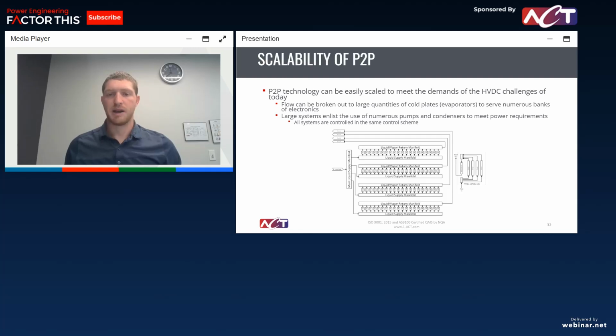So you can see on the bottom there just a picture of how we've done it before. Each of those little boxes that you can barely see there has 5 cold plates in it. So this is our look at what 400 cold plates would do. This system is doing 45 kilowatts of power dissipation. And we're looking at doing some systems that are significantly more than that, but the advantage of pump two-phase is it can scale to that. You just need to increase the number of cold plates. Sometimes you need more pumps and condensers, but they can all run through the same system and all use the same loop of fluid.